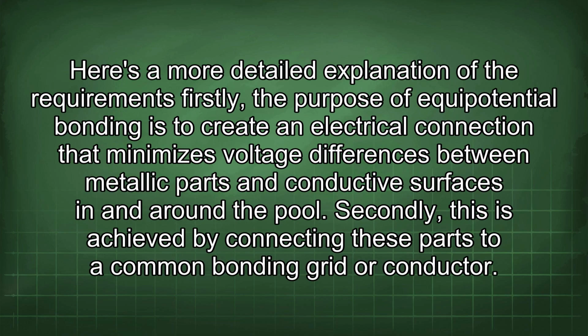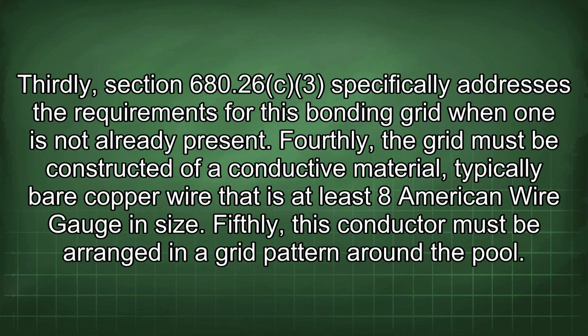Here's a more detailed explanation of the requirements. Firstly, the purpose of equipotential bonding is to create an electrical connection that minimizes voltage differences between metallic parts and conductive surfaces in and around the pool. Secondly, this is achieved by connecting these parts to a common bonding grid or conductor. Thirdly, Section 680.26 specifically addresses the requirements for this bonding grid when one is not already present.